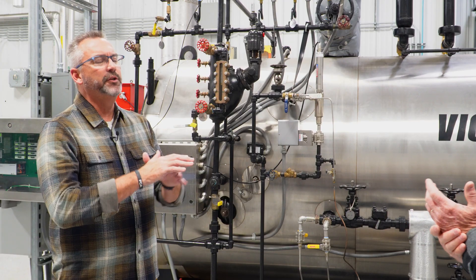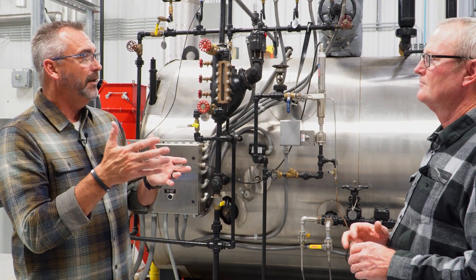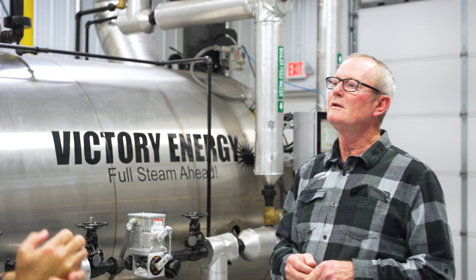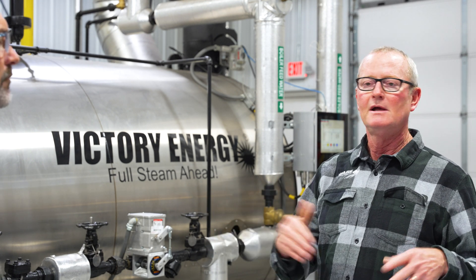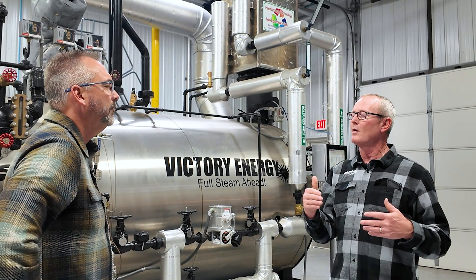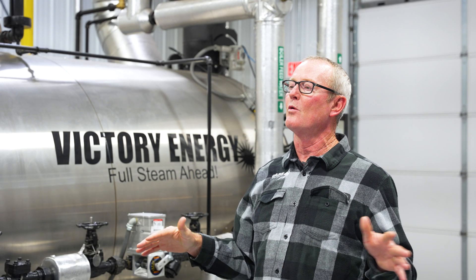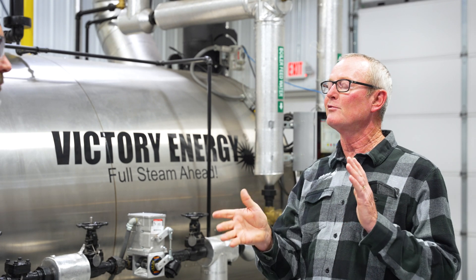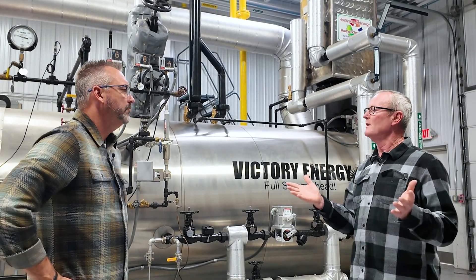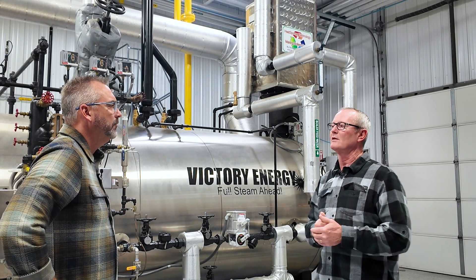We do both permanent boiler systems and rental boiler systems. So as a tip when you're calling in about a rental boiler: we ask them about the process. They need to tell us how their process works. Do you have a steady steam load — same load all the time, a little more heating at night, a little less during the day — or is this a batch process, meaning you open a valve up, throw steam in for 30 minutes, then drop off and have almost no load for another hour before doing another batch? Those are the ones where our flags go up and we ask, how does your actuator work? The same questions apply to permanent installations too — we want to get the same information so we know exactly what the operation is going to look like.